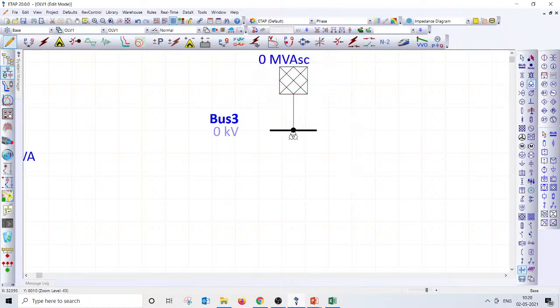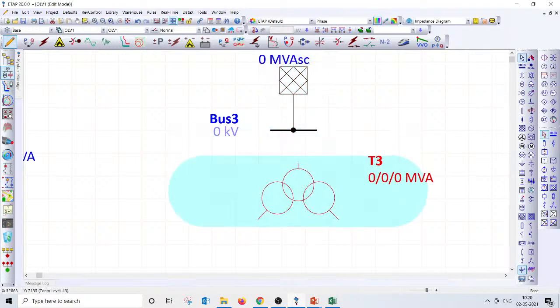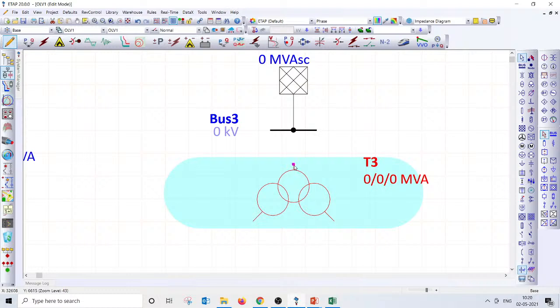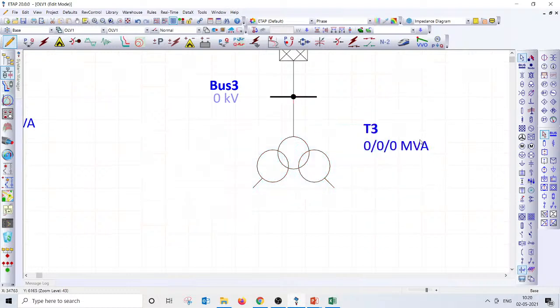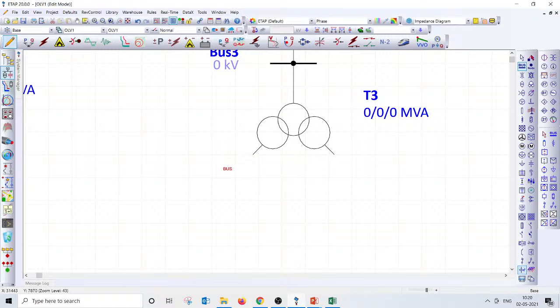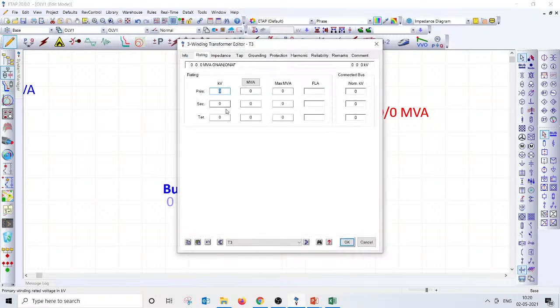ETAP allows you to model only up to a maximum of 3 winding transformers. You cannot really model multi-winding transformers, but if you are familiar with solar plants, you may even go up to 5 winding transformers, right? How many of you have used 5 winding transformers?